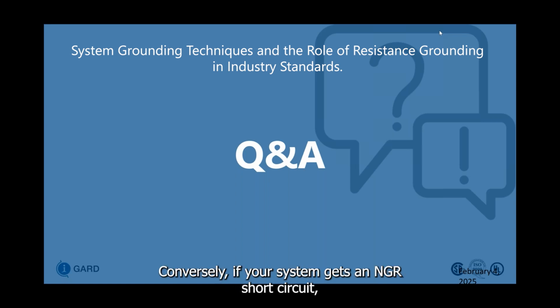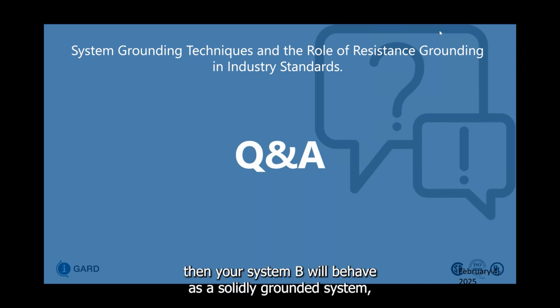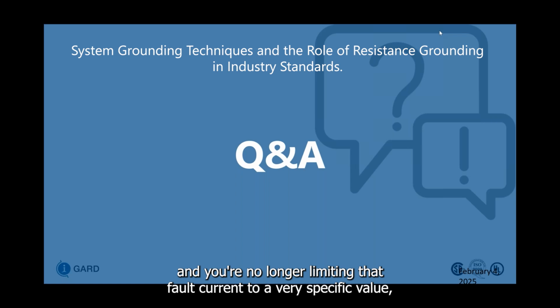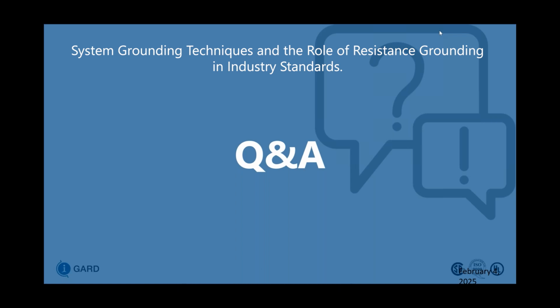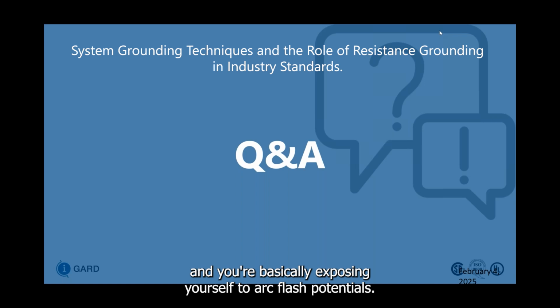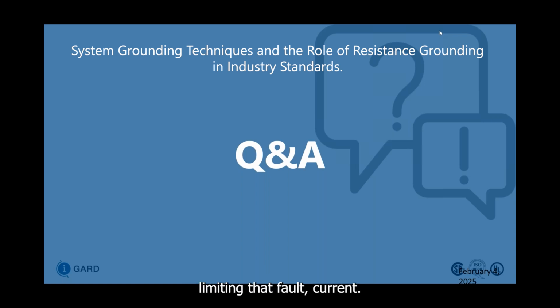Conversely, if your system gets an NGR short circuit, then your system will behave as a solidly grounded system, and you're no longer limiting that fault current to a very specific value. And you're basically exposing yourself to arc flash potentials since we're no longer limiting that fault current.